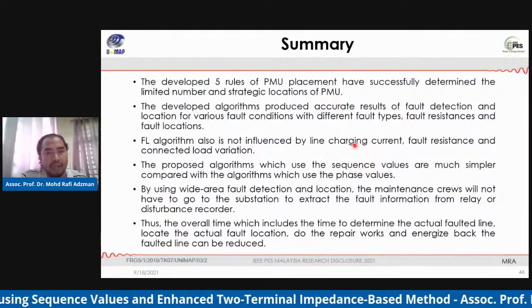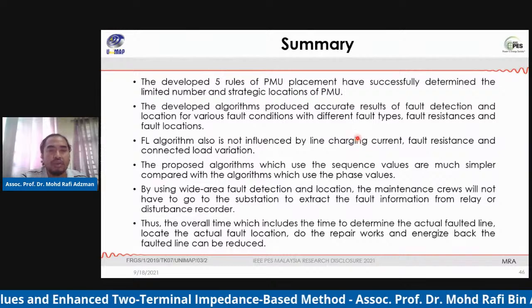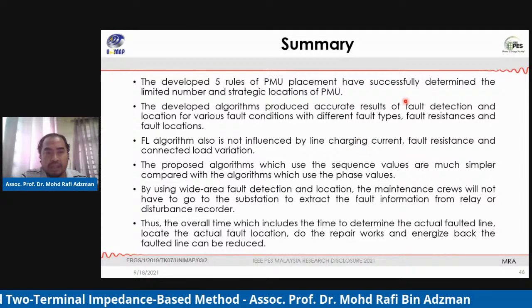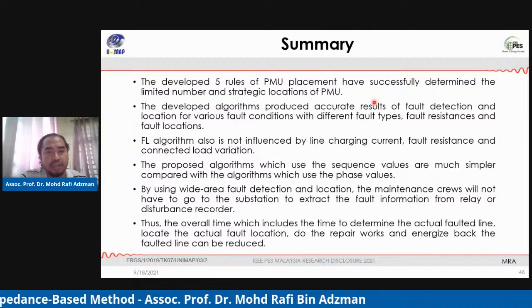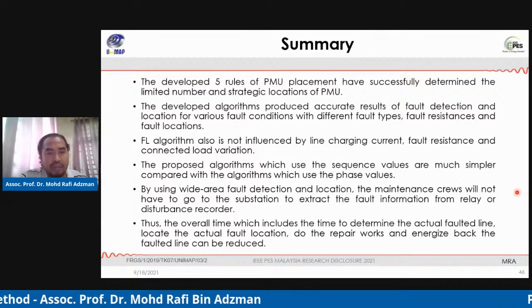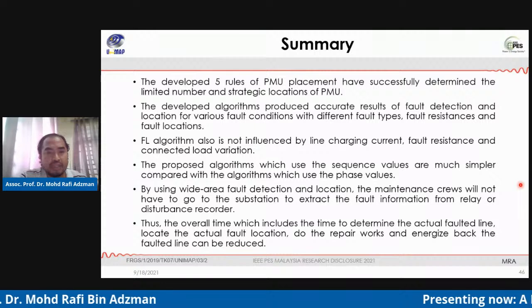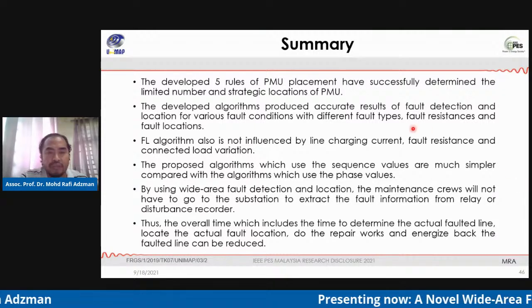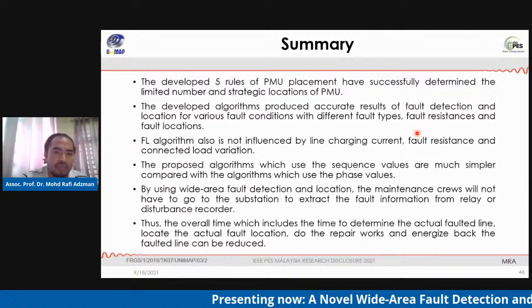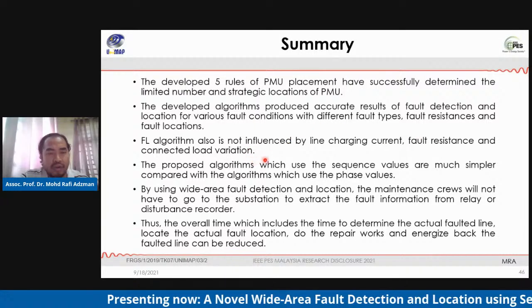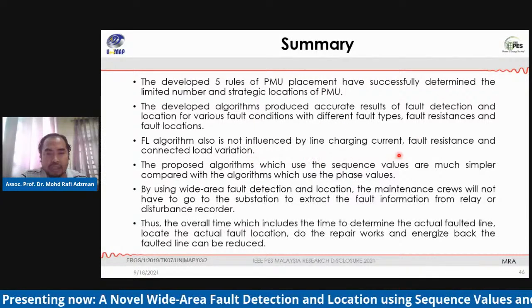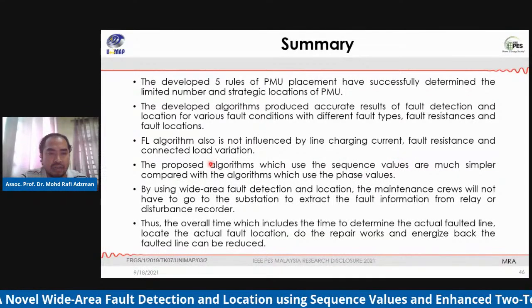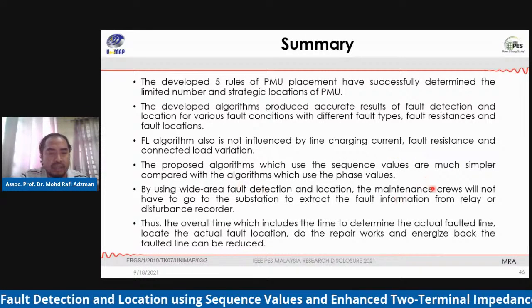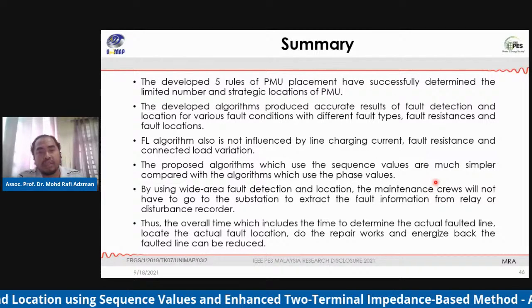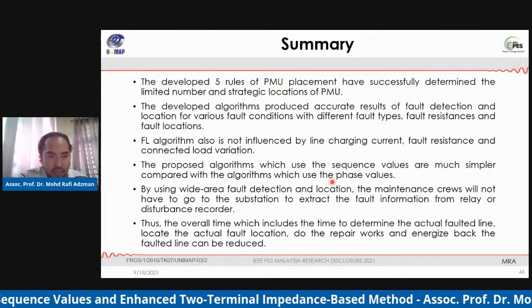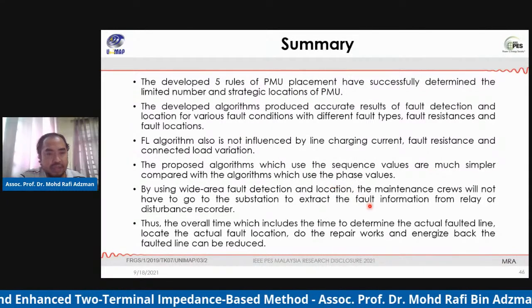For the summary, the developed 5 rules of PMU placement have successfully determined the limited number and strategic locations of the PMU. The developed algorithm produces accurate results of fault detection and location for various fault conditions with different fault types, fault resistance, and also fault locations. The fault algorithm is not influenced by the line charging current, fault resistance, and also the connected load variations. The proposed algorithm, which uses the sequence values, is much simpler compared with the algorithm which uses the phase values.